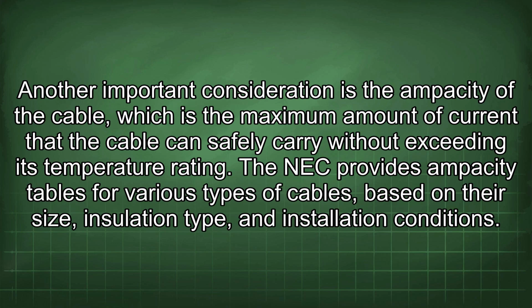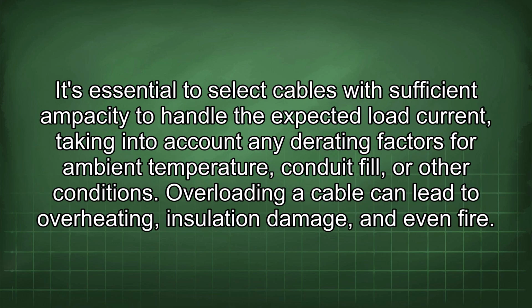Another important consideration is the ampacity of the cable, which is the maximum amount of current that the cable can safely carry without exceeding its temperature rating. The NEC provides ampacity tables for various types of cables based on their size, insulation type, and installation conditions. It's essential to select cables with sufficient ampacity to handle the expected load current, taking into account any derating factors for ambient temperature, conduit fill, or other conditions. Overloading a cable can lead to overheating, insulation damage, and even fire.